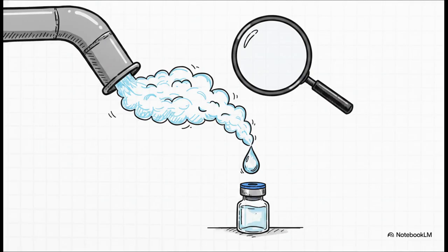First up, let's look at clean steam. When you utilize clean steam to sterilize those product contact surfaces, that steam must literally condense to water that meets WFI quality standards. But it isn't just about the water quality. The physical properties of the steam itself are highly regulated. You've got to implement strict controls over the steam's dryness, and you need to make sure that non-condensable gases are tightly controlled. Why? Because those factors directly impact the actual efficacy of the sterilization process itself.